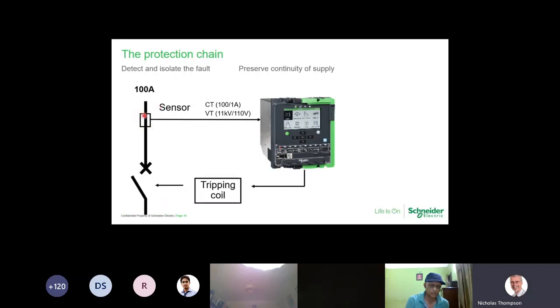sensor, which is there. We've got an electrical link to the protection relay. Then we've got an electrical link to our tripping coil. The tripping coil, incidentally, is going to be housed inside the circuit breaker itself. The circuit breaker typically will have very strong springs inside it, and you will find the bigger the current, or the larger the voltage, the higher the voltage, the bigger the springs are going to be, because they need that amount of force to open the circuit breaker or close it. So we use springs for closing as well.